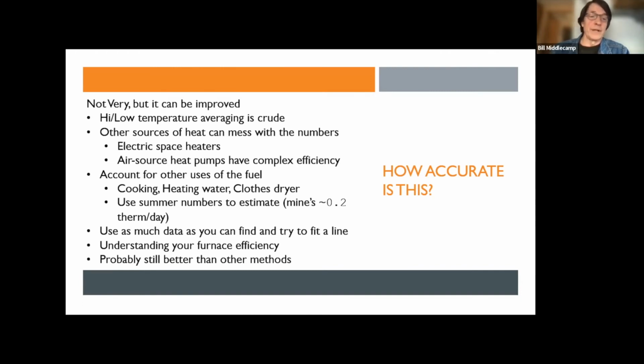I said that I have an air source heat pump, and that's really complicated to figure this kind of thing out because they have varying efficiency or coefficient of performance, as they call it. So you might have to try and figure out how to subtract that out. And again, accounting for other uses of the fuel, that's a crude measure. Mine is about 0.2 therms per day. But if you use as much data as you can find over as long a time as possible, plot it out, and then try to fit a line to it, the slope of the line should match these formulas. And if you extrapolate that slope down to the coldest temperature, you can come up with the same numbers. It is still, I think, better than a lot of other methods. So I actually used it a second time.